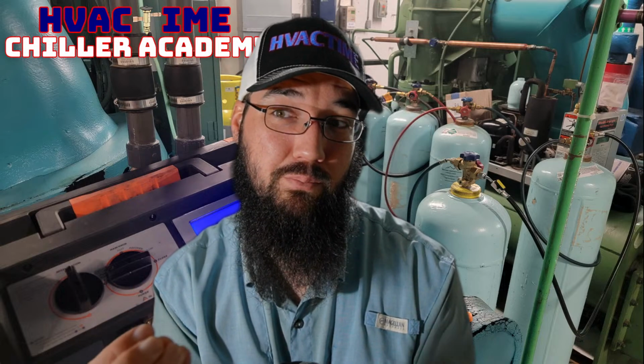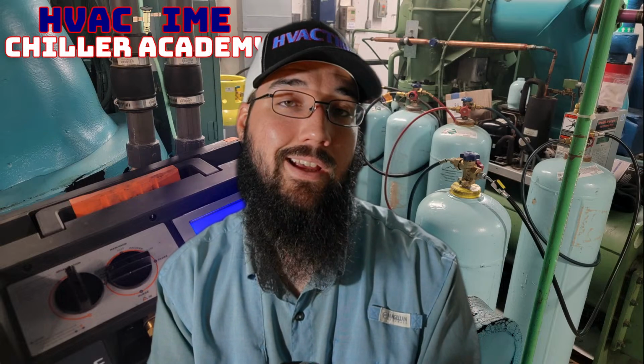So I don't recommend using our standard off-the-shelf solder, because that's not the same and it won't melt the same way. The solder filler they use is designed to melt at a very specific temperature to prevent a complete blowout. What we have is meant more for actual line connections, like holding couplings together so they don't blow out. A lot of our solders will make a hold strong enough that you'll burst the pipe before you burst the joint. So I don't recommend that.